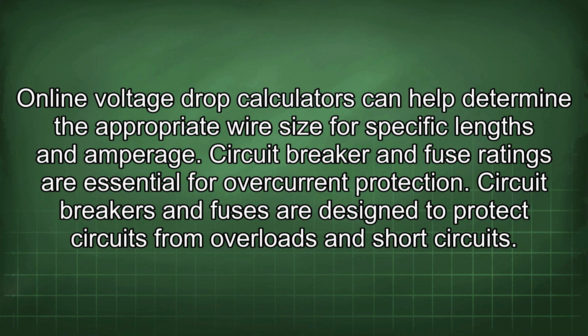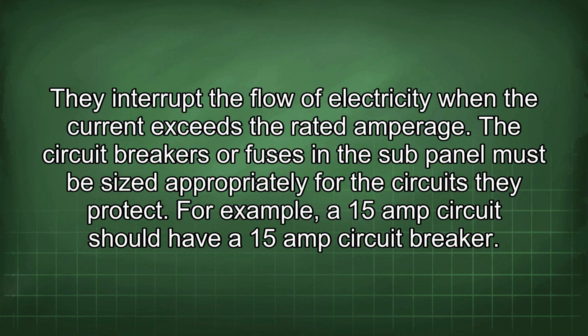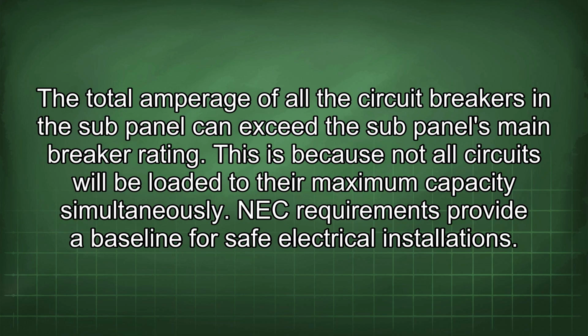Circuit breaker and fuse ratings are essential for overcurrent protection. Circuit breakers and fuses are designed to protect circuits from overloads and short circuits. They interrupt the flow of electricity when the current exceeds the rated amperage. The circuit breakers or fuses in the sub-panel must be sized appropriately for the circuits they protect. For example, a 15 amp circuit should have a 15 amp circuit breaker. The total amperage of all the circuit breakers in the sub-panel can exceed the sub-panel's main breaker rating. This is because not all circuits will be loaded to their maximum capacity simultaneously.